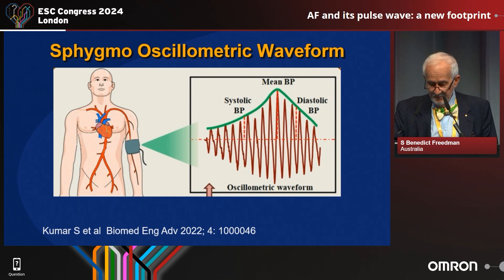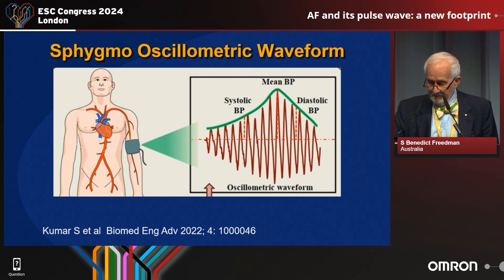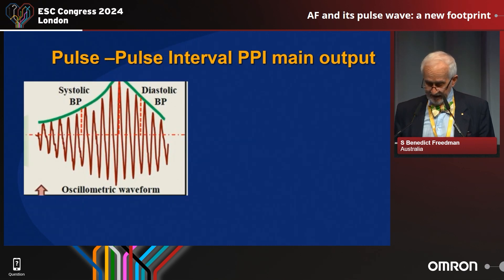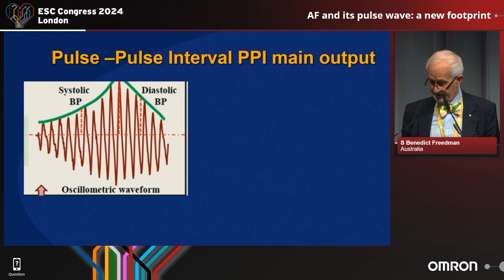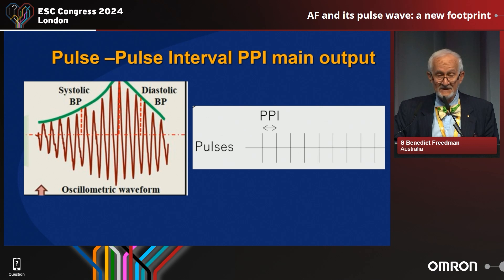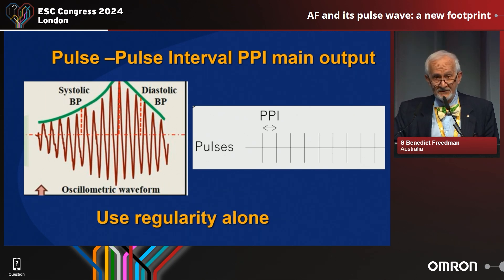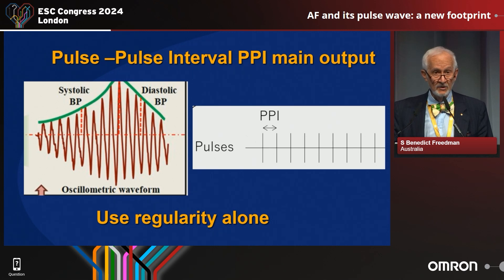Here we see a cuff and an oscillometric waveform on the right-hand side. This is from a study reported in 2022, Kumar et al. in Biomedical Engineering Advances. You can see that what is done here when looking for atrial fibrillation is just using the peak-to-peak variation — looking at the peaks of those pulse waveforms, it's called pulse-to-pulse interval, the peak-to-peak interval. This variability and irregularity is what is used in most algorithms to detect atrial fibrillation.